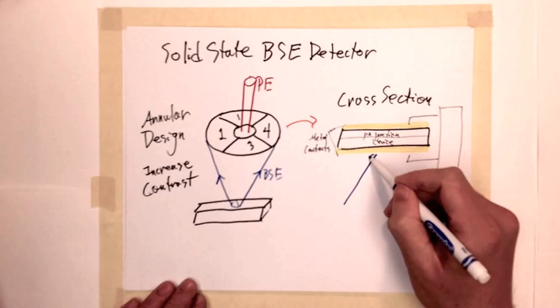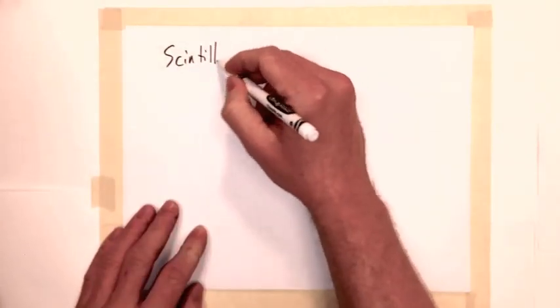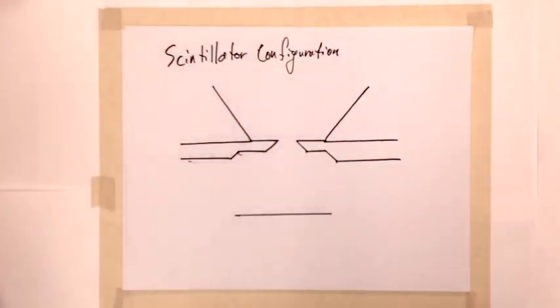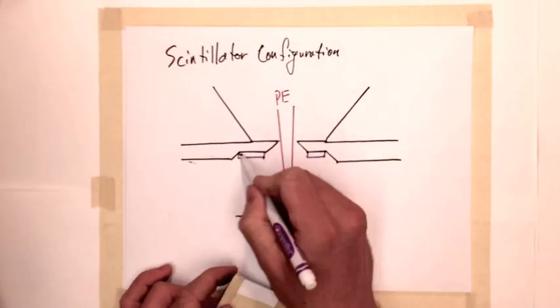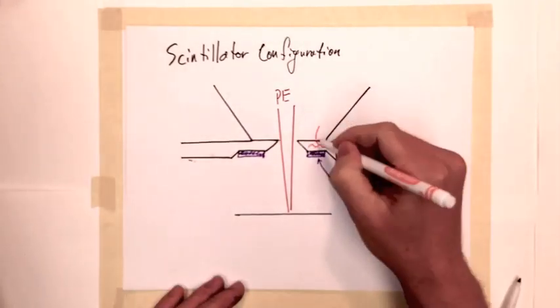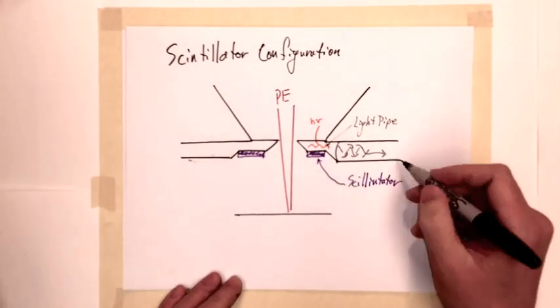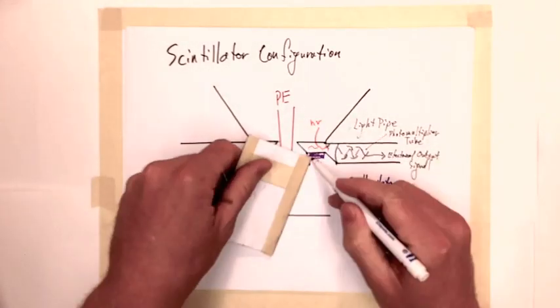Backscattered electron detection can also be realized using a scintillating device configuration, very similar to that of the Everhart Thornley detector. A scintillating film is placed under the aperture, and incident electrons cause the material to emit a photon proportional to the electron energy. This will be collected by a light pipe and fed into a photomultiplier tube. The PMT produces an electrical signal that can be amplified for image formation.